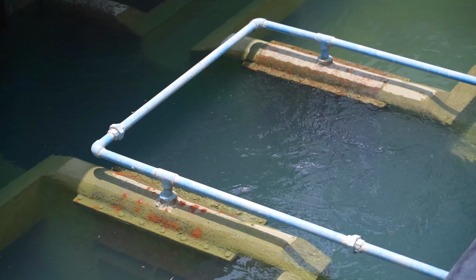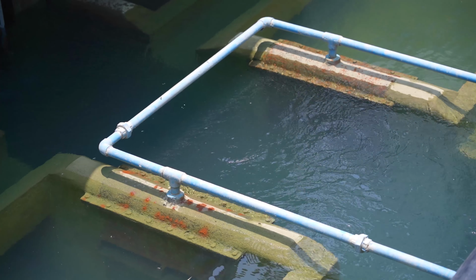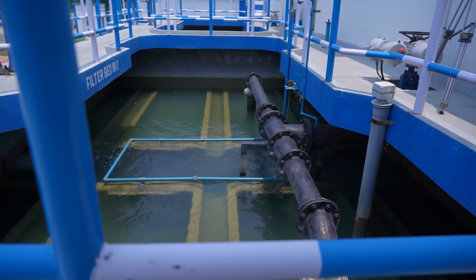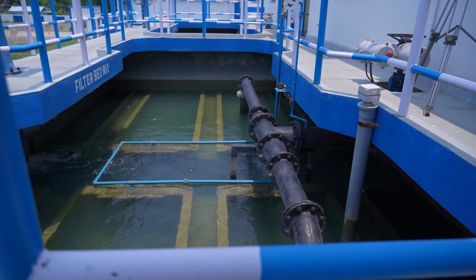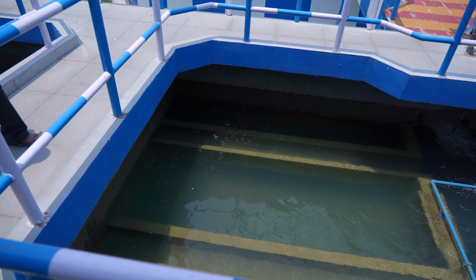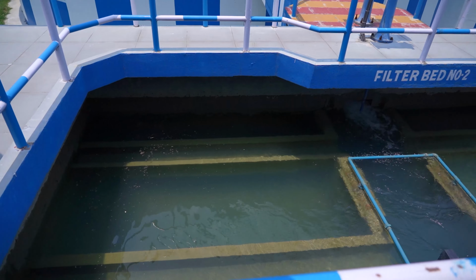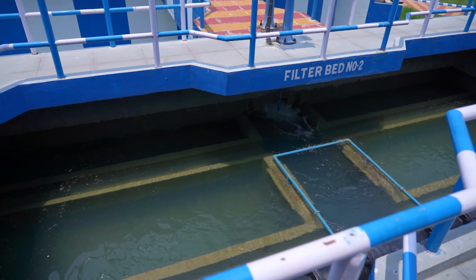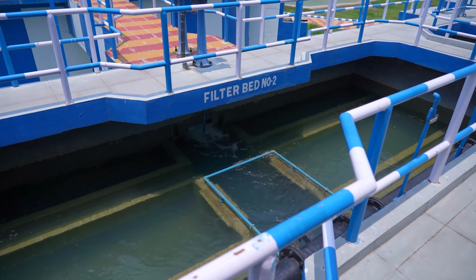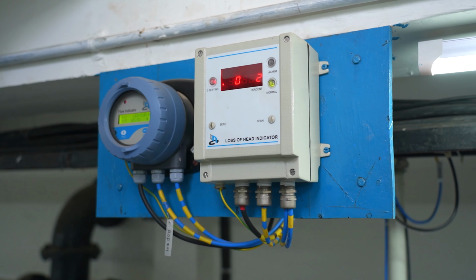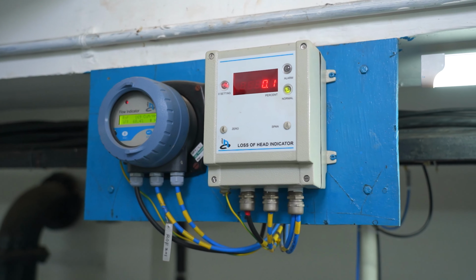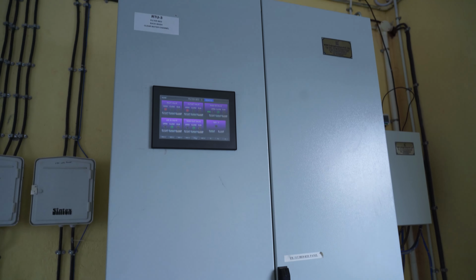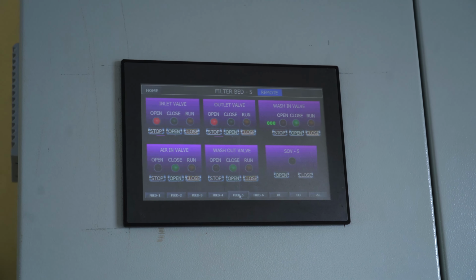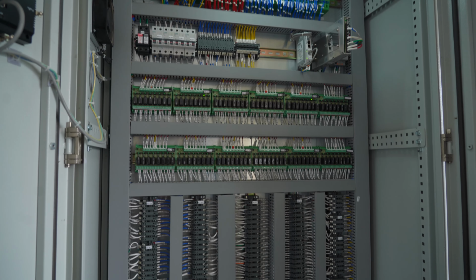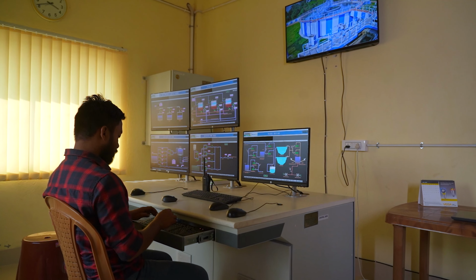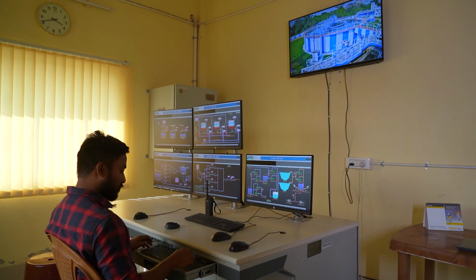The filter beds, while working to remove the impurities from water, also get choked in due course of action, which is measured from sensors associated with the sand bed like ROF and LOH. Data collected from these helps the operator to decide which bed should go for backwash and manage the whole process very smoothly through the various interlocking processes of the SCADA system.